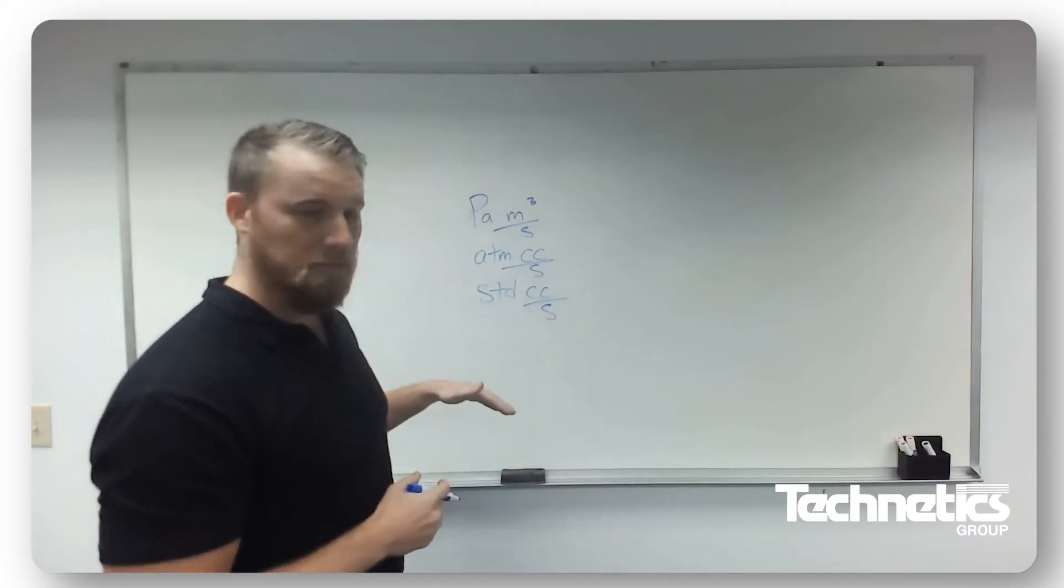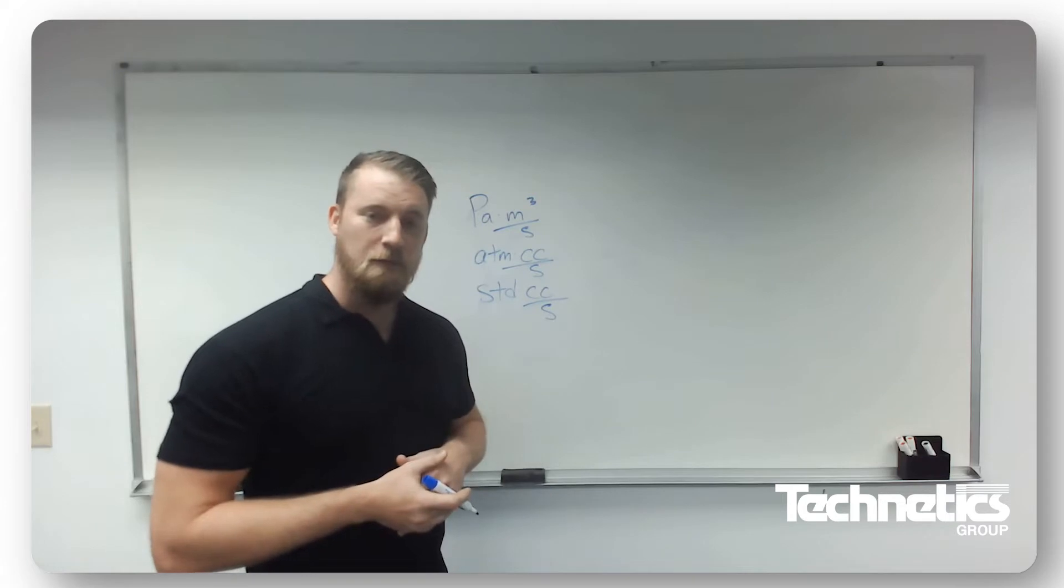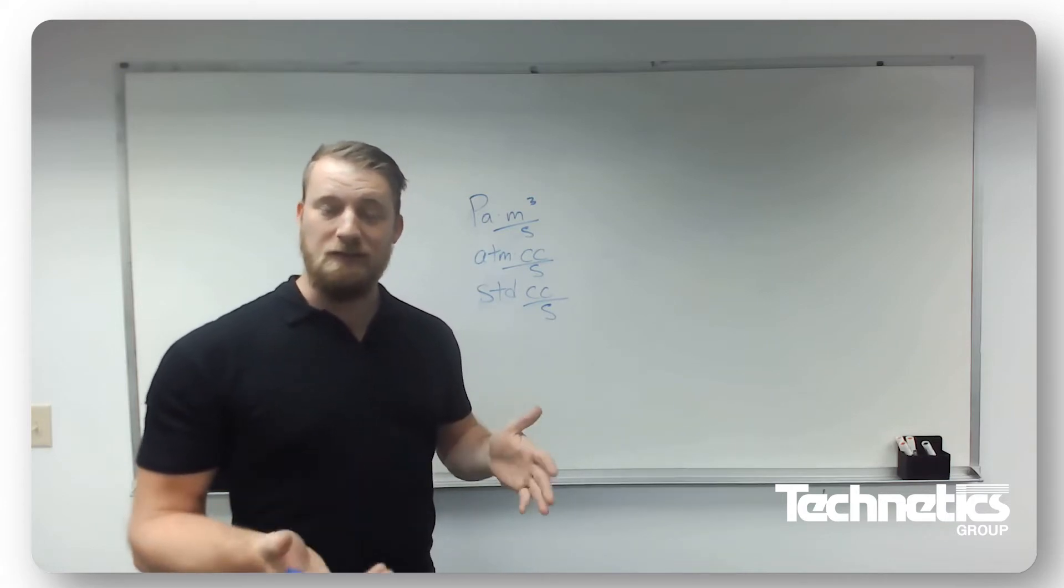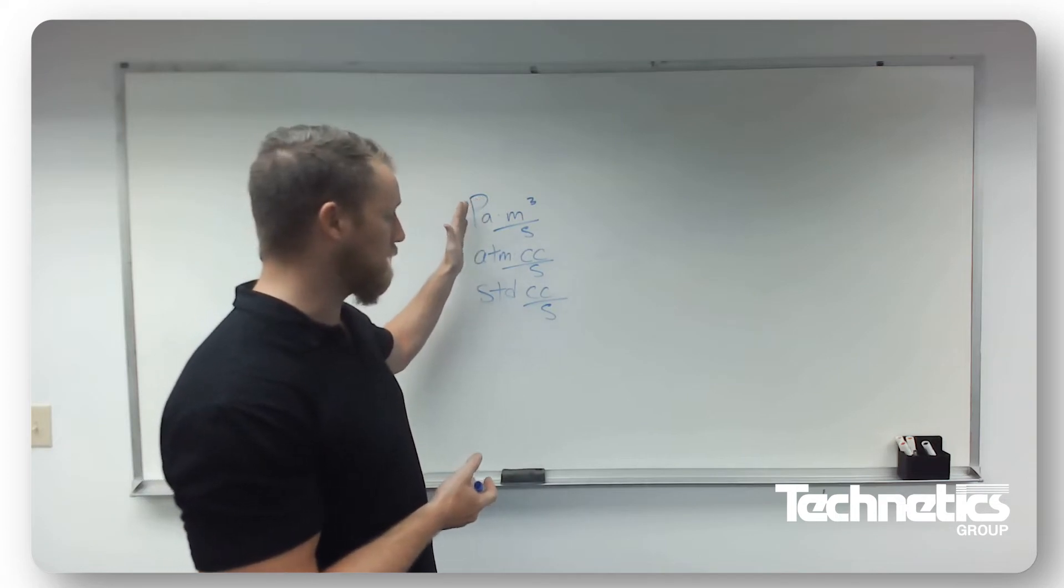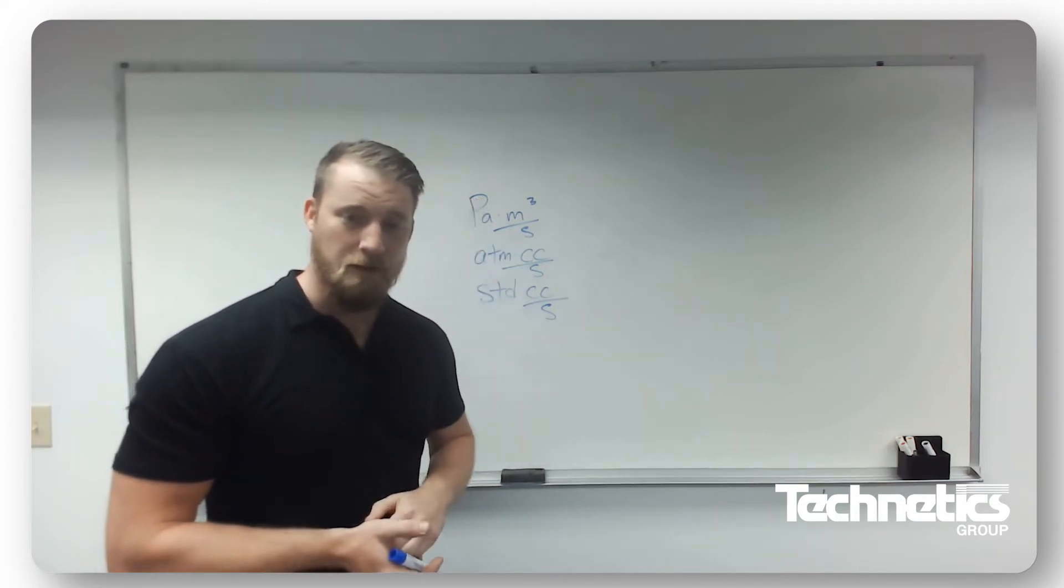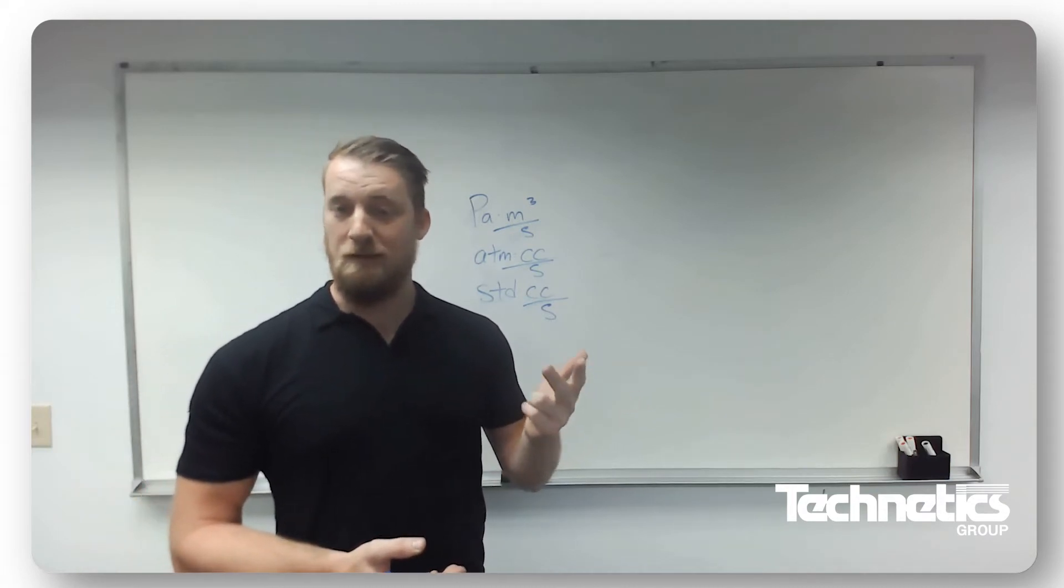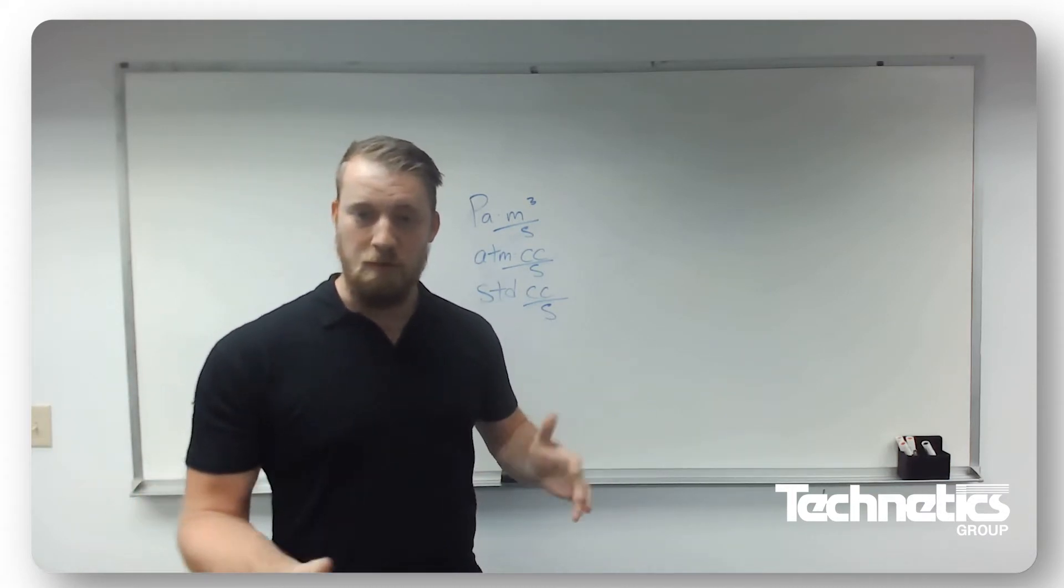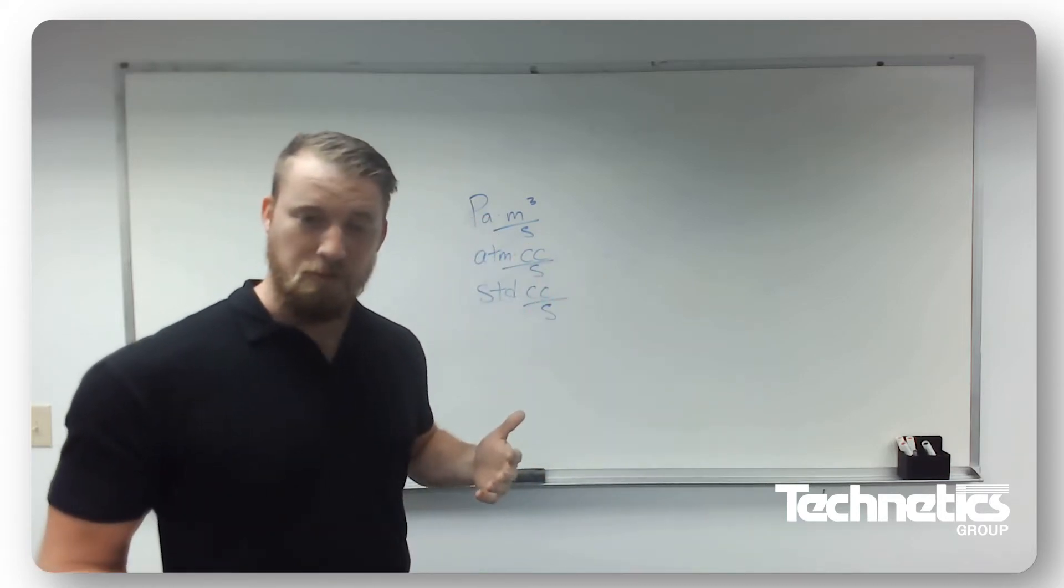Now, all of these units are basically communicating the same information with some conversion factors. And what that information actually is, is a molecular flow rate. The number of molecules that leak out over a unit of time. If you remember the ideal gas law, if we know the pressure, volume, type of gas, and temperature, we know how many molecules there are. Or in our application, the number of molecules that leak out over a given period of time.